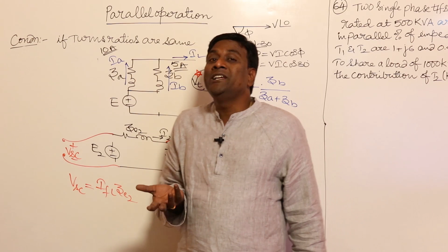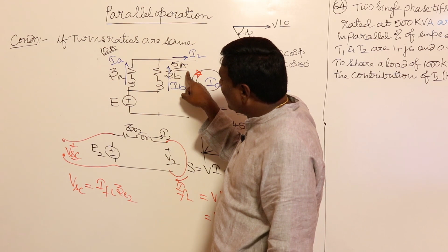Now you kept one transformer of 10 kVA and a transformer of 5 kVA. Now in the combination, in order to exploit the full 15 kVA, whenever it is supplying 10 kVA, it has to supply 5 kVA. Means that if full load current of 10 amperes is going through this, at the same time, for the same voltage, full load current of 5 amperes should go. So how much is the short circuit voltage to be supplied to circulate full load currents for transformer B? It is going to be 5 into ZB, which should be exactly equal to full load current multiplied by ZA. So 10 kVA multiplied by ZA should be equal to 5 kVA multiplied by ZB, or 10 amperes multiplied by ZA should be equal to 5 amperes multiplied by ZB.